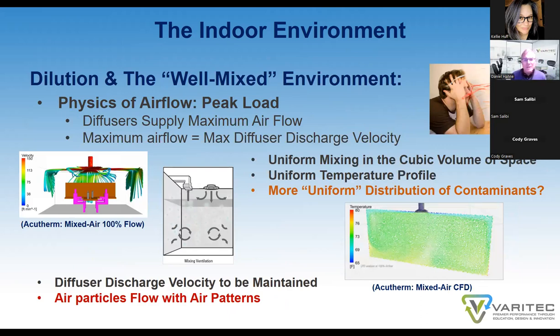Well, when do we see, again, peak airflow at diffusers? Well, that's at our peak summer design condition. In Phoenix, Arizona, it's our summer months. In June, when it's 115, maybe even now 120 outdoors, our actual peak summer design condition is monsoon, when we have a lot of moisture and humidity in the air. However, we have to ask the question: when we do inject air per conventional wisdom at high velocity, is uniform mixing actually occurring in the environment?